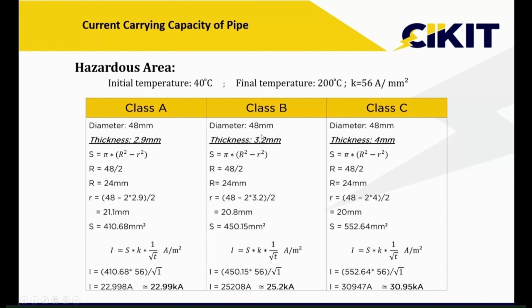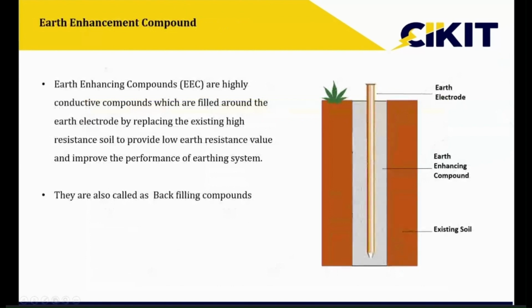So I have to increase the size or go for a higher class pipe. When we are working in a hazardous, that is oil and gas area, we should keep in mind this final temperature of the particular area. The current carrying capacity of a material will be different for a safer area and a hazardous area. When we are working in a hazardous area, we should use the final temperature as 200 degrees centigrade only. We should not use the previous one. So the second component is earth enhancing compound.